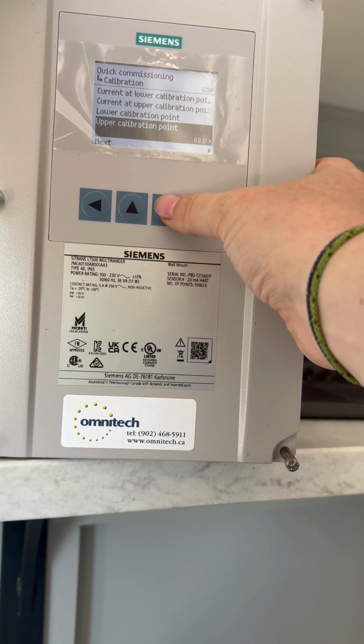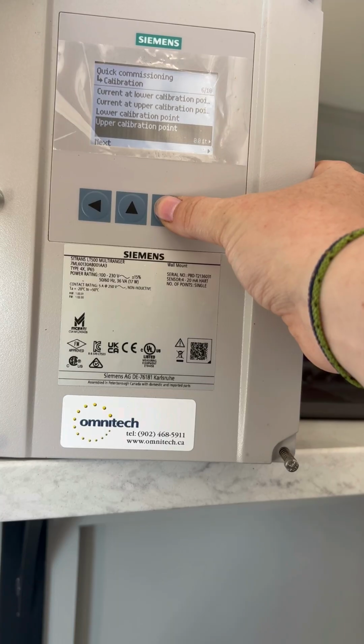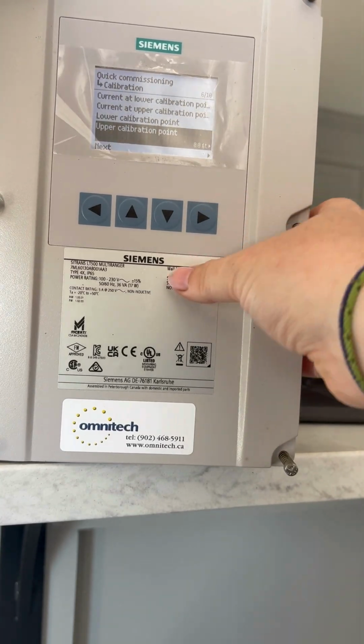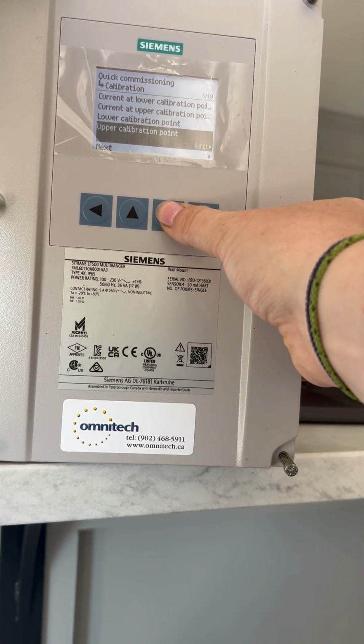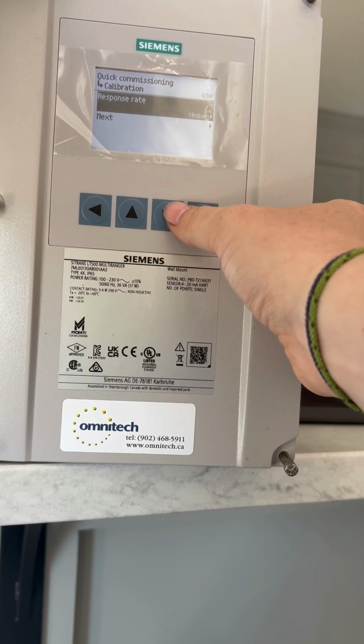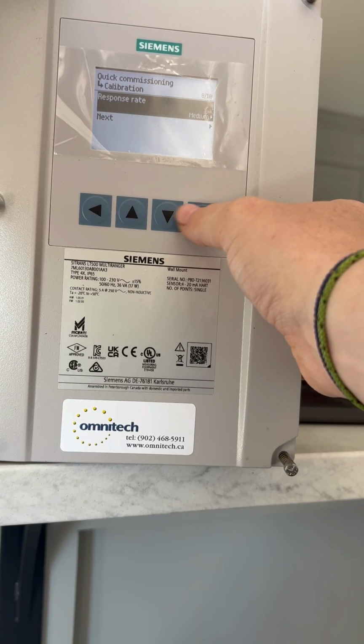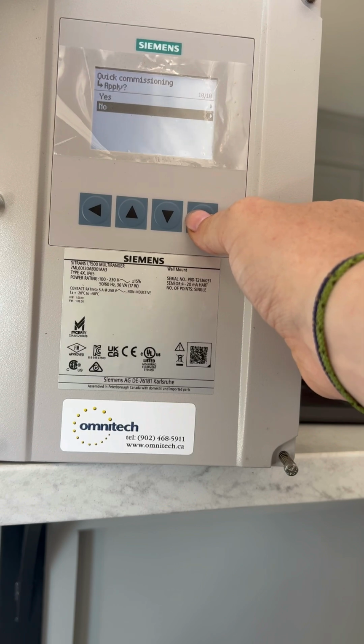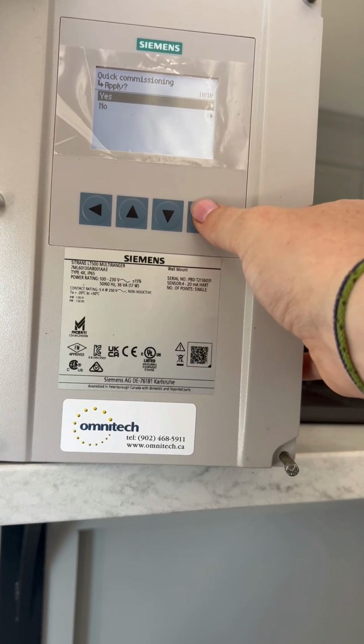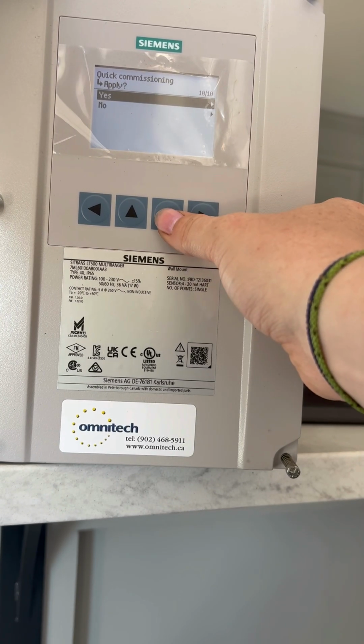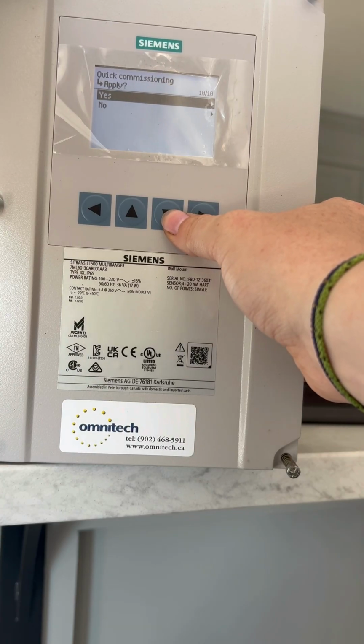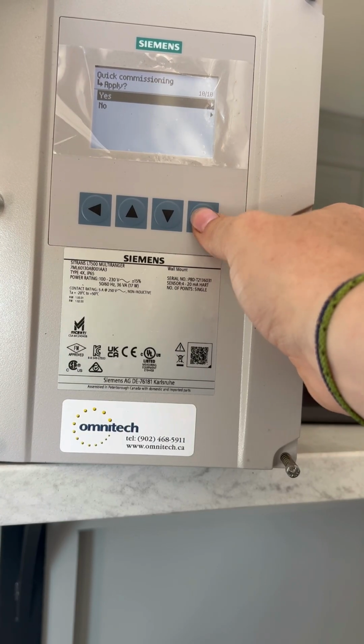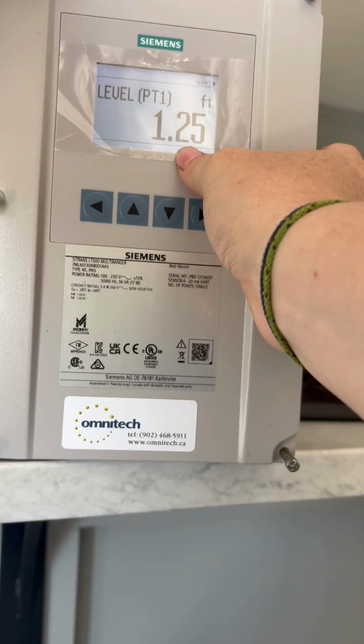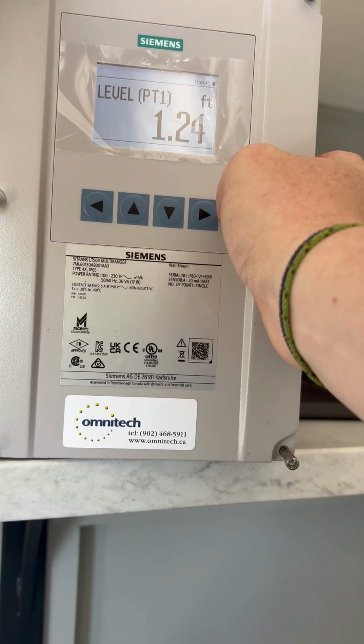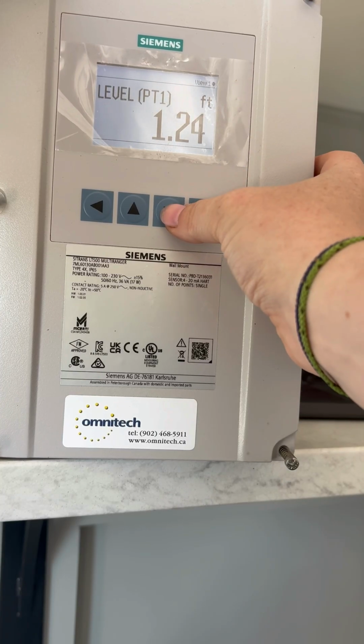And then again, I have my upper calibration as 0. That's saying once I got to the top, how high would I be? So 0 to 12 is my upper. Next, response rate, we're going to keep that on medium. And then I'm just going to say yes, I'm going to apply commissioning. If I went through it and realized no, I didn't want to do that, or I want to make a change, you can just say no. But I'm going to say yes. And as you can see, we have that 1.25, so that's 0 to 12.